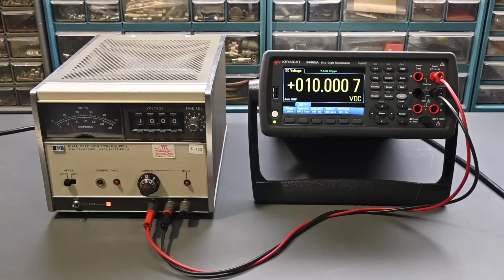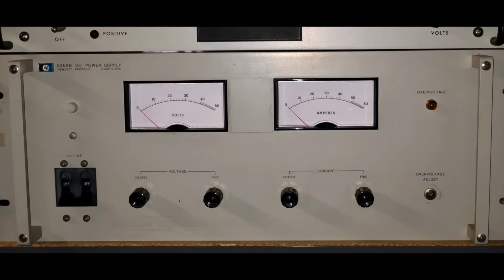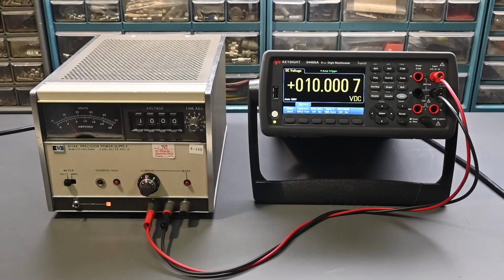Now, another way that this can be used is the 6114A can control a power supply like my HP 6269B. The 6269B is a 0 to 40 volt, up to 50 amps supply, but it has knobs to set the current and the voltage. So it has a constant current mode or constant voltage mode. And this power supply can be used to control either the constant current or the constant voltage. For example, if you're using it in the constant voltage mode, this power supply will set the voltage output of the 6269B with the stability and the accuracy that this 6114A has, but now you have up to 50 amps of current capability. So it's like taking this 6114A and increasing its current up to 50 amps. That's pretty cool, to have a very stable and accurate power supply, but with up to 50 amps of current. So I think that'll be very useful to use it that way as well.